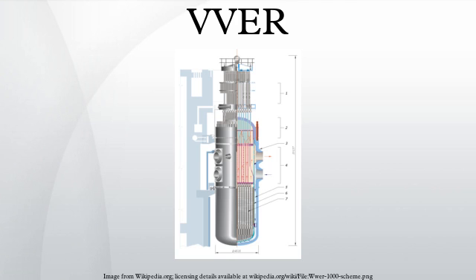If there is an emergency, a reactor shutdown can be performed by full insertion of the control rods into the core. In the primary cooling circuit, water is kept under constant pressure to avoid boiling. Since the water transfers all the heat from the core and is irradiated, integrity of this circuit is most crucial. Four subsystems can be distinguished: reactor water flows through fuel rod assemblies and is heated by the nuclear chain reaction; a volume compensator regulates pressure employing self-regulation of the saturated steam-water interface and by means of electrical heating and relief valves.